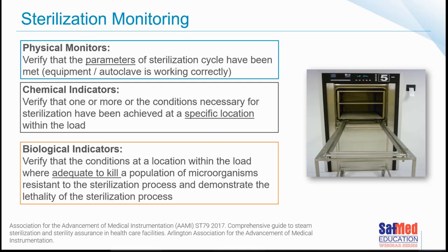We use biological indicators to verify that the conditions at a location within the load were indeed adequate to kill a known population of microorganisms that are resistant to steam sterilization or the sterilization process at hand. And that, of course, demonstrates the lethality of the sterilization process, how lethal it is, how able it is to kill microorganisms.